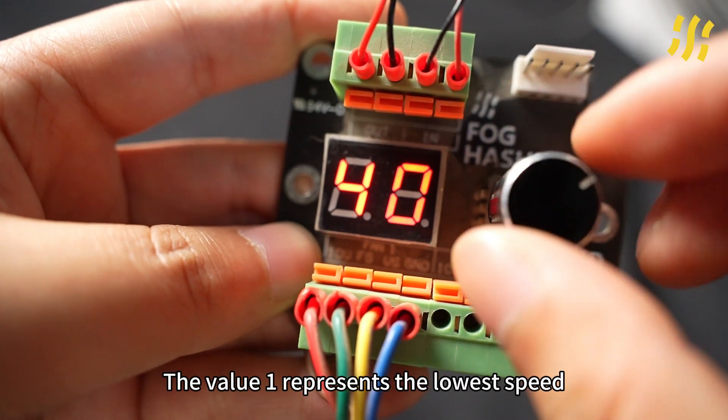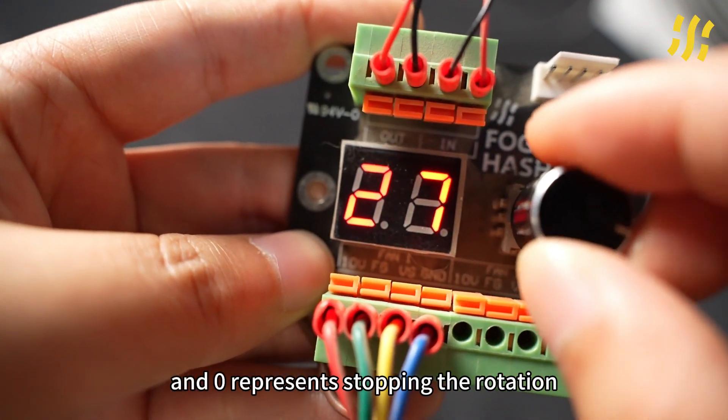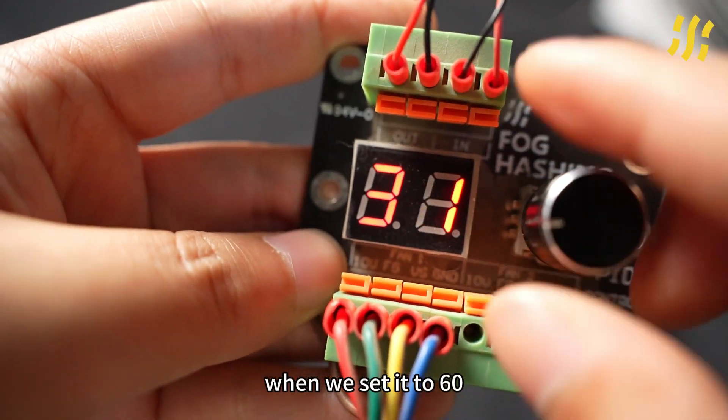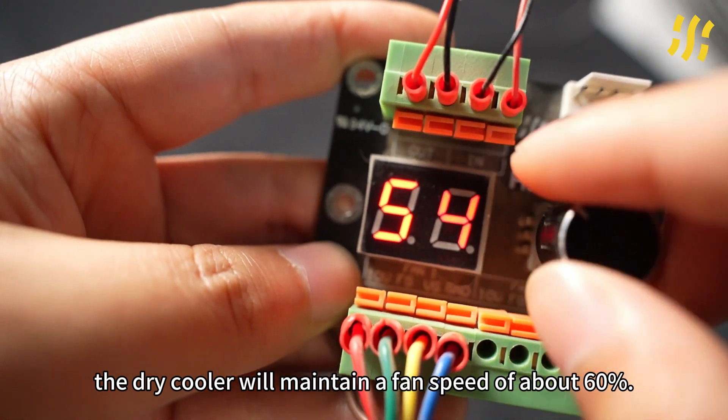The value 1 represents the lowest speed, 99 represents the highest speed, and 0 represents stopping the rotation. For example, when we set it to 60, the dry cooler will maintain a fan speed of about 60%.